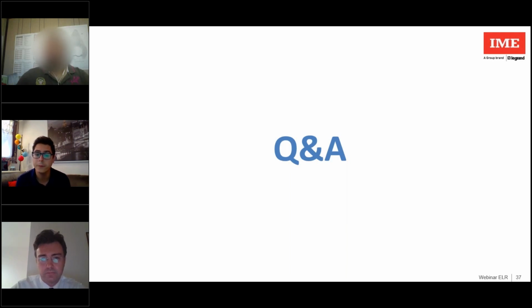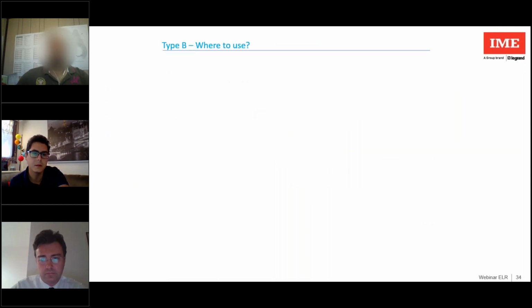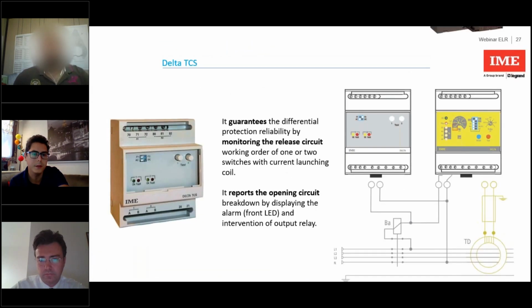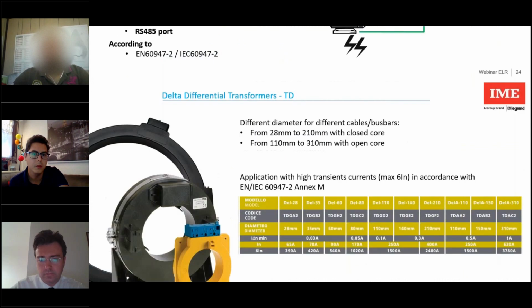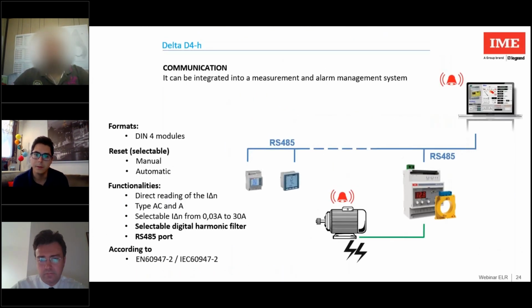Yes, the Delta D4H. We find in this slide one of the last added to the series. You can remotely see the differential current. You can find the protocol on our website, or if you want ready-to-use software, you can use our EDM Evo software. So you can remotely see the differential current, but also reset or test the relay.